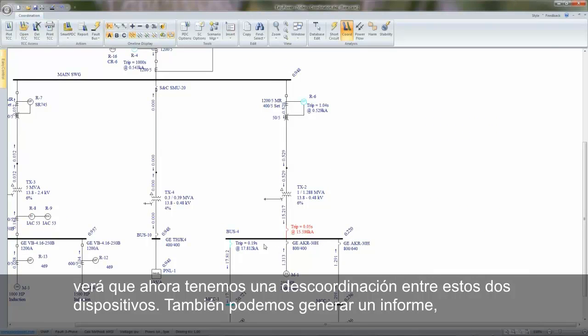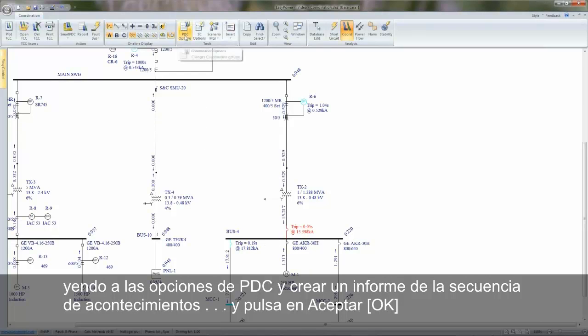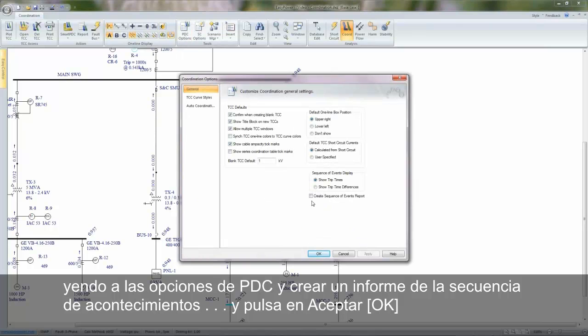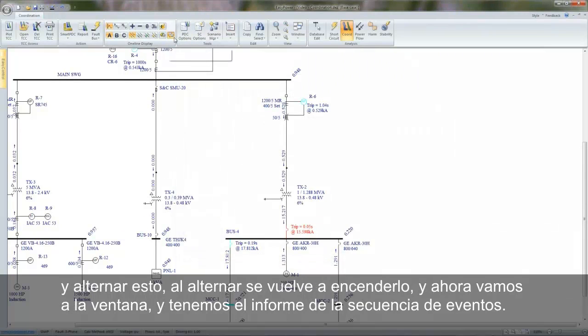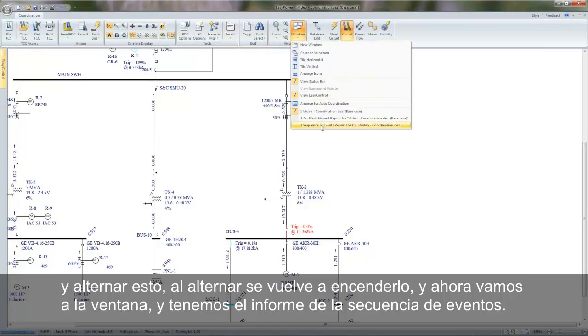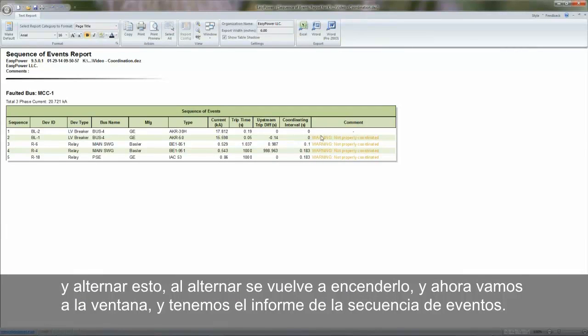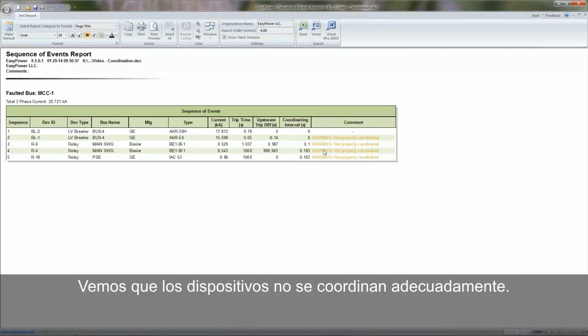We can also get a report out by going to the PDC options, create sequence of events report, hit OK, and toggle this, toggle it back on, and here we go to Window, and we have the sequence of events report. We see devices are not properly coordinated.